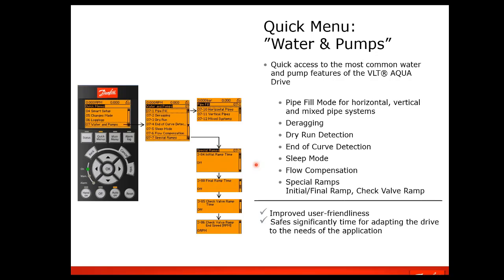Derag is also one of the quick menu items in the water and pump application level. This infogram here is showing through the quick menus, the Q3, or Q7 excuse me, is the water and pump area. And of other water and pumping applications, you see derag is one of the features here, as well as pipe fill, dry run, end of power curve, sleep mode, flow compensation, and some of the special ramping. But when you go into that group, it will take you into the derag in here. This one's just showing other types of parameters in the quick menu.